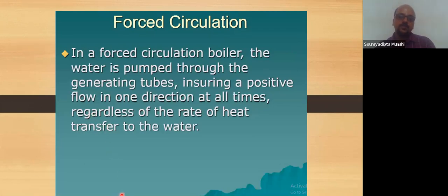So now is the forced circulation. Natural circulation is limited to a boiler drum operating pressure of approximately 175 kg per centimeter square. If a boiler drum operates beyond this capacity, the circulation has to be assisted with mechanical pumps. So now we have to use mechanical pumps to overcome the frictional losses.